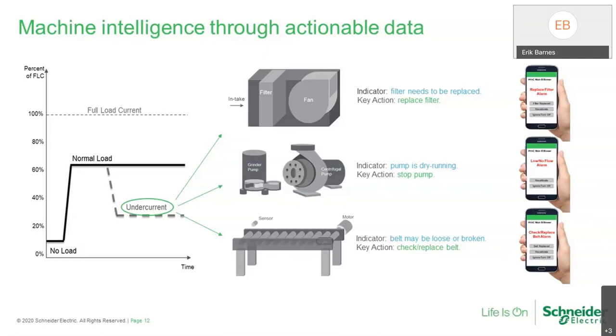So we have the ability to set an undercurrent alarm where your typical filter gets to the dirty status where it needs to be replaced. When that alarm triggers, you can alert maintenance. Maybe you have that sent back to your company, and you send them a filter, or maybe you send out a service tech to go replace the filter. There's lots of ways to add revenue and add value once you know what's going on with the equipment.